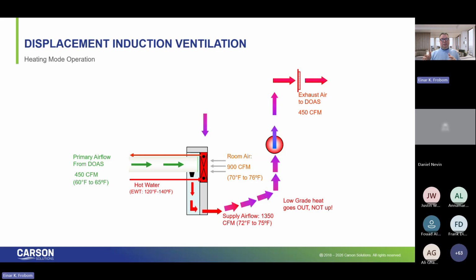The key point is we don't want really warm air going out of our diffusers. And we're able to do that because even though we're going to size the equipment for January 31st at 3 a.m. with no people, that's not where we're going to operate it. If I'm maintaining the room at 70 degrees, when we go into heating, we will warm up the air from the DOAS unit a little bit. We'll create that same induction process.